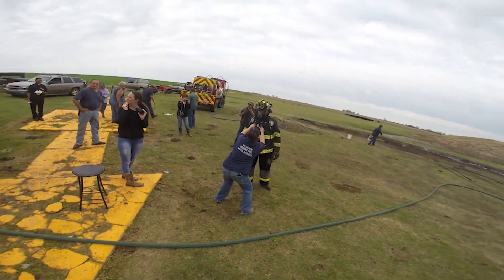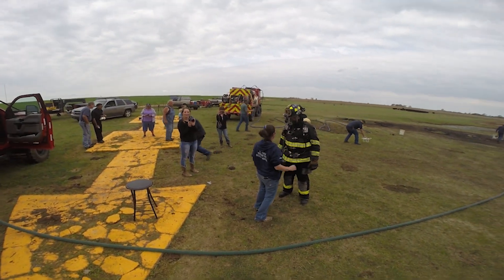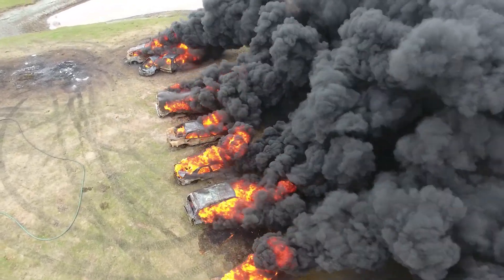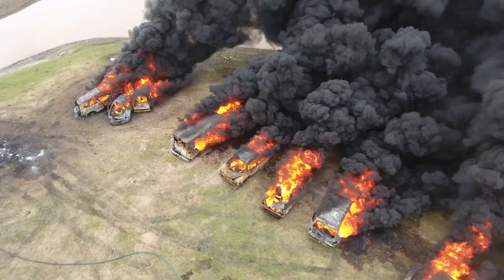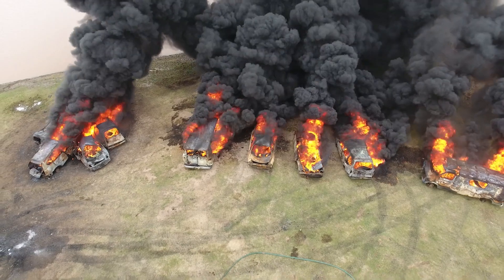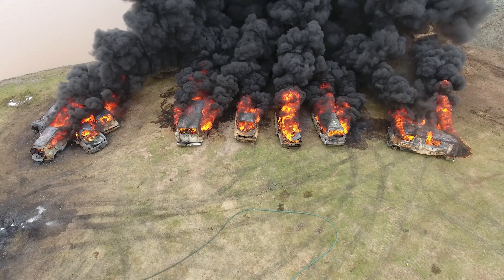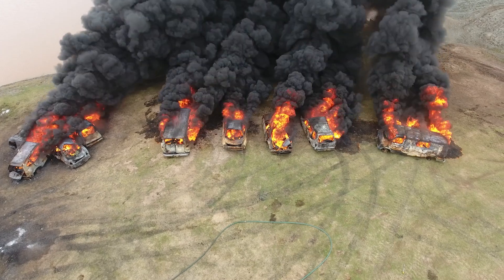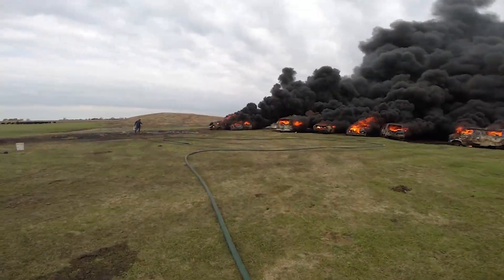Only a small percentage of water actually gets used. In 2001, a study was performed by the Los Angeles County Fire Department. In the study, they compared the effectiveness of water on fire versus compressed air foam systems — CAFs. Their point of measurement was to bring the temperature of the fire room to a level theorized to be survivable by the occupants. The quantity of water used and time needed to bring the room from 600 to 200 degrees Fahrenheit was recorded. The results showed that CAFs required 78.6% less water to achieve the target temperature of 200 degrees in 75.8% less time.